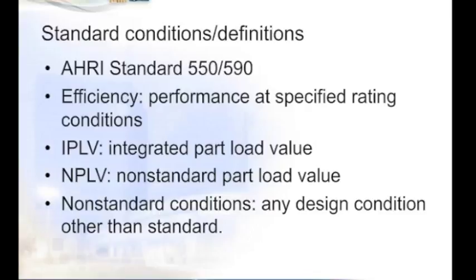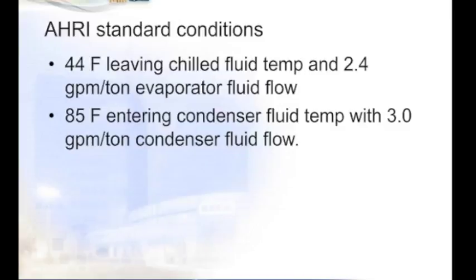So what are the AHRI standard conditions if you choose to use those? 44 degrees Fahrenheit leaving chilled fluid temperature, not necessarily water, because it might be glycol, it might be a variety of mixtures, and 2.4 GPM per ton evaporator fluid flow. Coupled with that, it's 85 degree entering condenser fluid temperature with 3.0 GPM per ton condenser fluid flow. Operation at any other condition is considered non-standard.